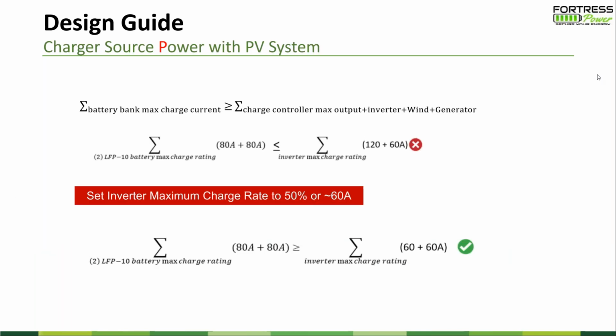And we look at the charger source power with the PV system. We'll talk about the more complicated system later, but in this slide we want to talk about the charger source. Usually you have a charger, whether it's a separate MPPT or an integrated MPPT, so you have to look at what inverter you're choosing. I'll take a typical example here. Say I have 2 lithium batteries, and the inverter charger from the grid can do 120 amps. Then 1 MPPT can do 60 amps from the Schneider system. Overall it's 180 amps. We recommend an 80 amp charge rate for each battery, so 2 would be 160 amps. 180 is over 160, so that's not recommended. Let's go to another route. So what do you do?